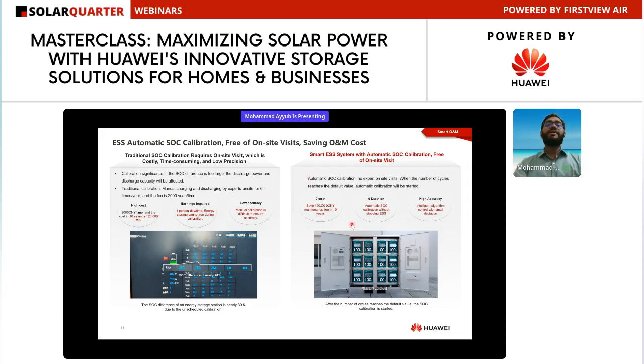Over time, say we install batteries today, after 1 year and 2 years the SOC difference between battery packs will continue to increase. For example, today one pack might be at 90% and another at 95%, a 5% difference, but after a year that 5% gap could grow to 10% or 15%.